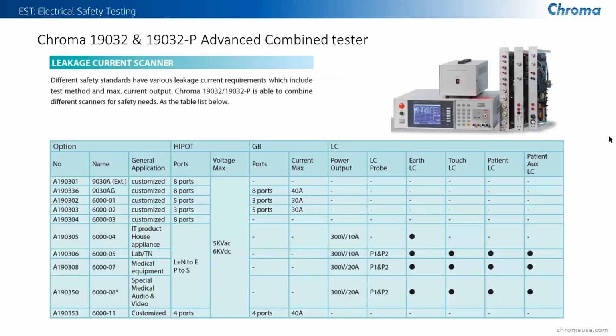I talked a little bit about the different scanner cards that plug into the back of this unit. These are the different options that we have. And with this, you can include up to 30 amps, 20 amps, 300 volt for doing the various types of line fault conditions and earth, ground, and neutral to simulate the fault conditions as well. And so these plug into the back. They're easy to set up and control. And again, they can be programmed internally to simulate those faults for the variations that we had talked about earlier.